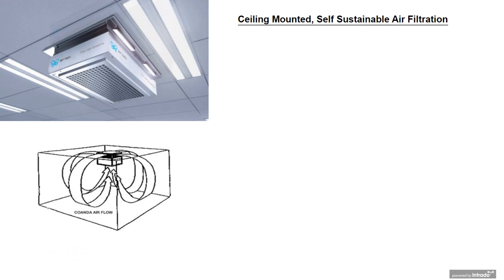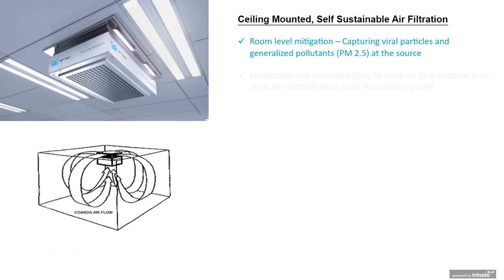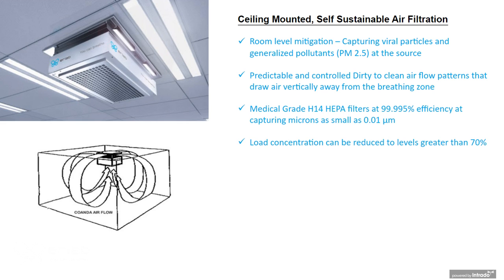Then there's ceiling-mounted self-sustainable air filtration systems that are not integrated into the HVAC system, and they just process the air. These provide room-level mitigation. They capture viral particles, generalized pollution, PM 2.5 at the source, and they draw air up and away from the breathing zone of the occupant, which is extremely critical. When they disperse the air, so they drive the air up vertically, they disperse it horizontally and create what's known as a Coanda airflow effect. And as you see here in this diagram, it basically creates an airflow curtain, and it ensures that we're taking all the polluted air that's down and around, up and away from the breathing zone and continuously to move the air.